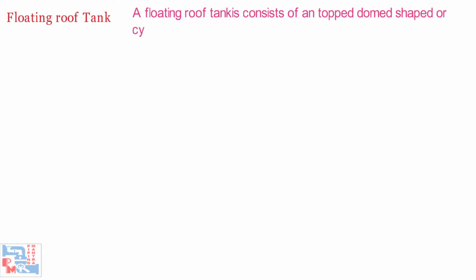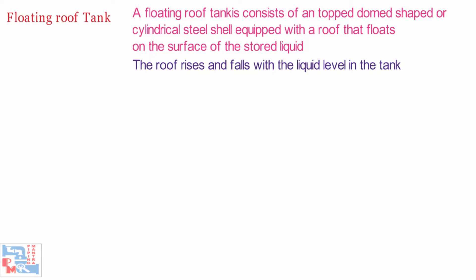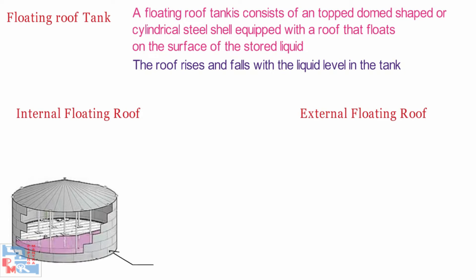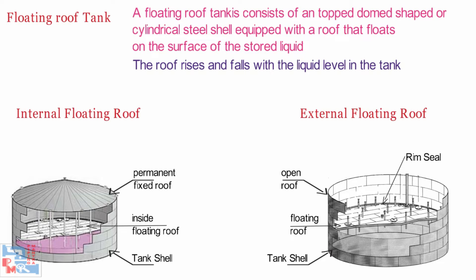Now comes the Floating Roof Tank. A floating roof tank consists of an open-topped, dome-shaped or cylindrical steel shell equipped with a roof that floats on the surface of a stored liquid. The roof rises and falls with the liquid level in the tank. There are two types: Internal Floating Roof and External Floating Roof. Internal Floating Roof Tanks have both a permanent fixed roof and a floating roof inside the tank on the liquid surface, or supported on pontoons several inches above the liquid surface. External Floating Roof Tanks are equipped with a rim seal system which is attached to the roof perimeter and contacts the tank wall, sliding against it as the roof is raised and lowered.